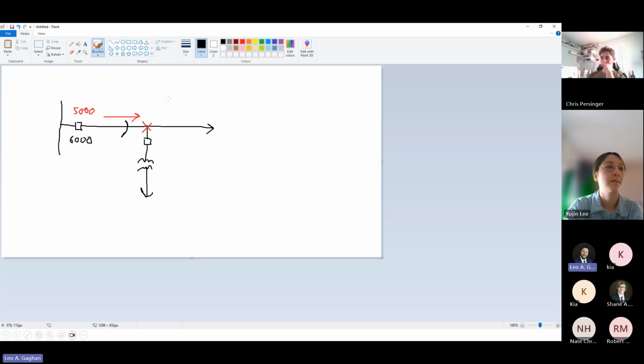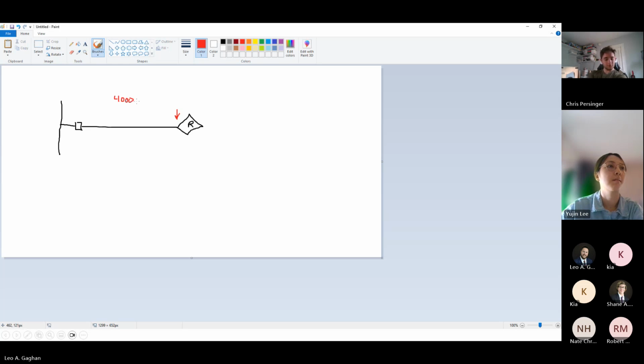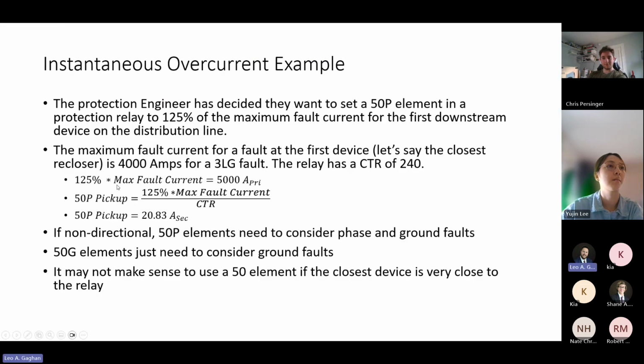So, okay, we can show that. We said recloser, so we'll draw that symbol. Put a little R. So, fault right there, we're going to see 4,000 amps. Recloser. So we want to set it to 125% of that 4,000 amps. That would be 5,000 amps primary. So we will not operate for that 4,000. It's going to take a little bit more.